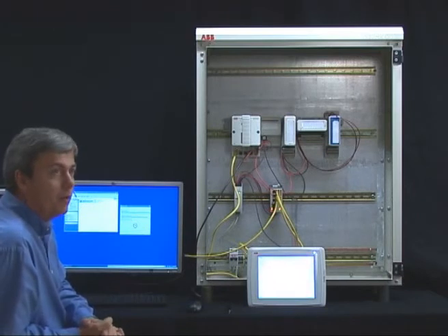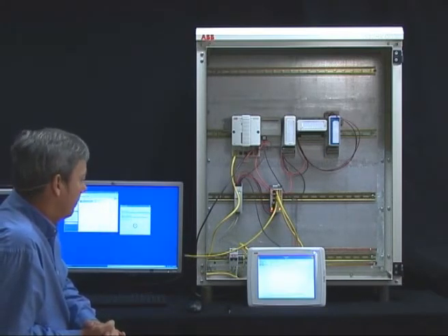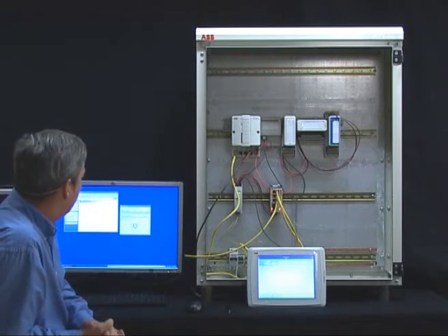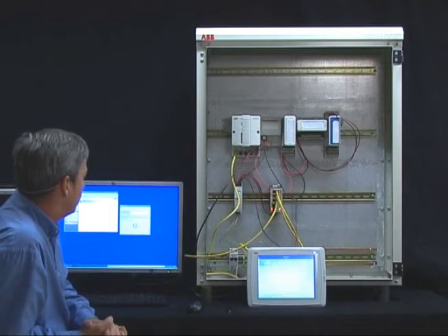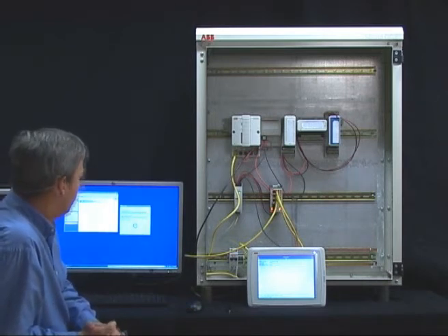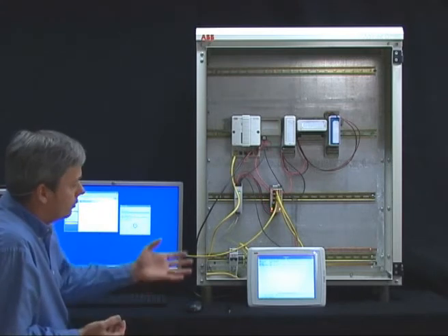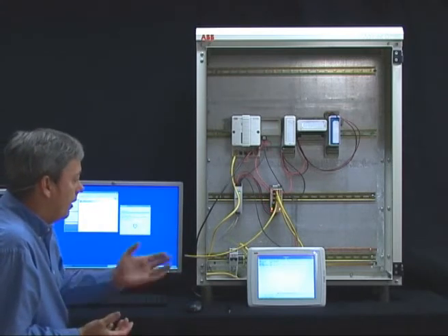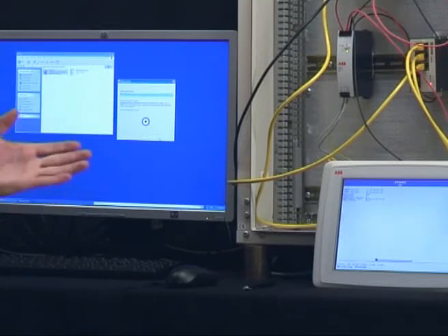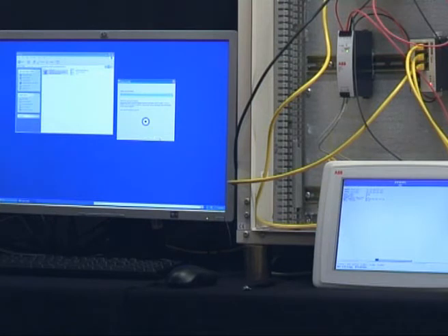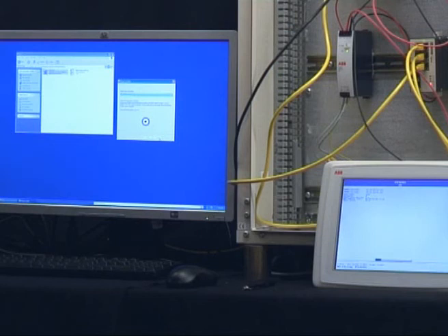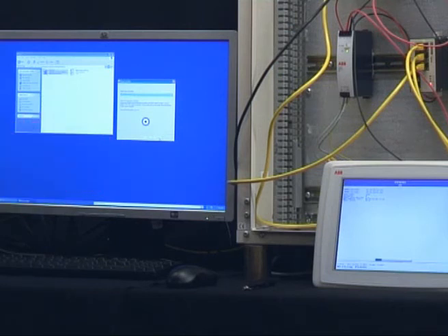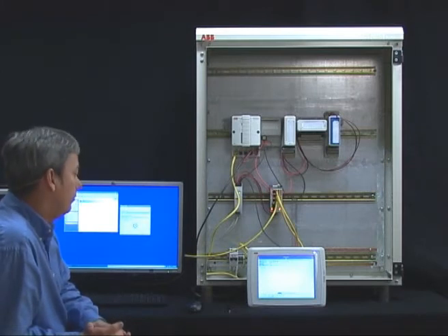This takes some time, so we can wait for that. What is happening is that we first download the firmware and then we write this to the flash memory in the panel. When we have done this, it is safely stored in the panel, so next time it will load the new firmware if you power off and power on again. You can see the progress on the panel screen as we are downloading and starting up with the new firmware.